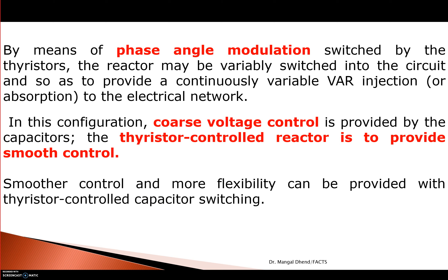By means of phase angle modulation you can control the phase angle of TCR and have variable power absorbed from the system. TCR power can be varied by controlling angle alpha. In this configuration, coarse voltage control is provided by the capacitor — it will be step control, not smooth variation. TCR will provide fine, smooth control. Smoother control and more flexibility can be provided with thyristor controlled capacitor switching.